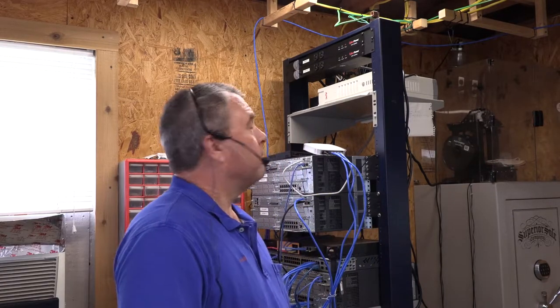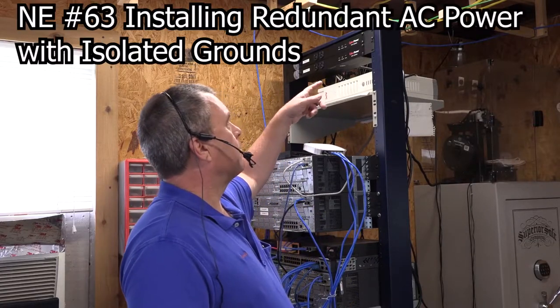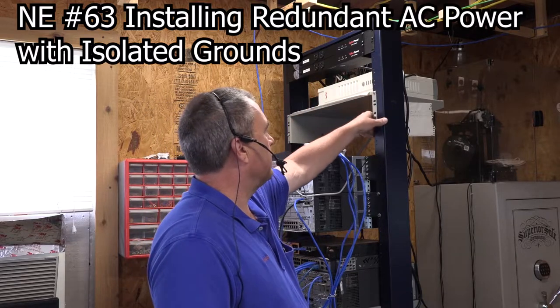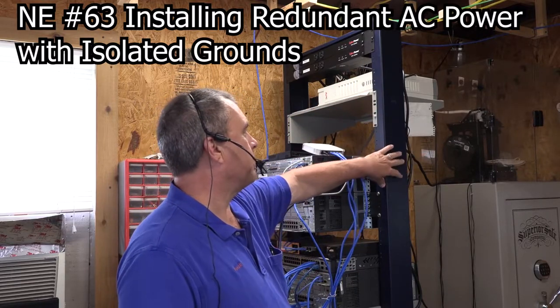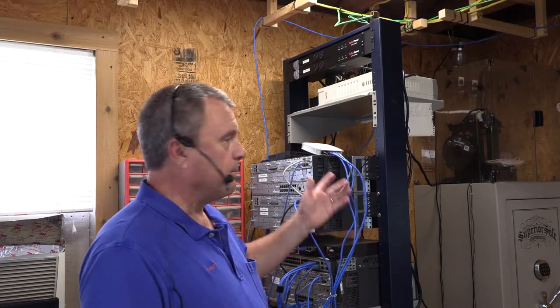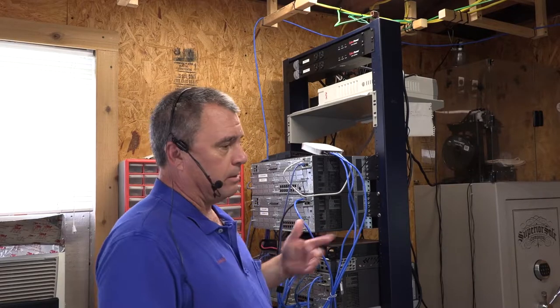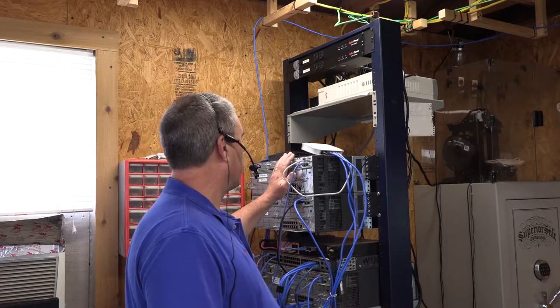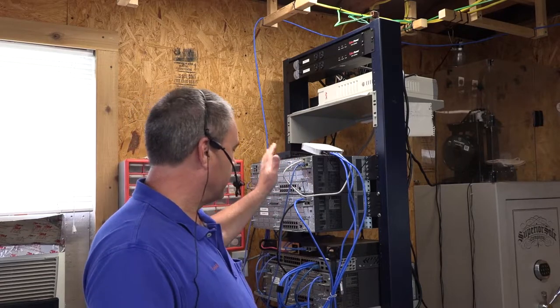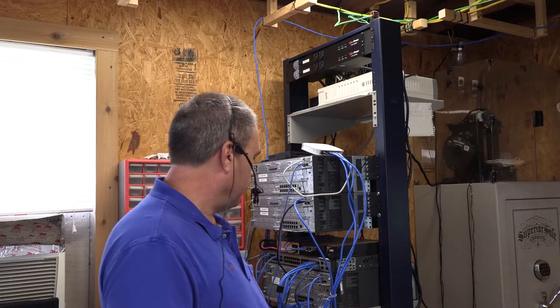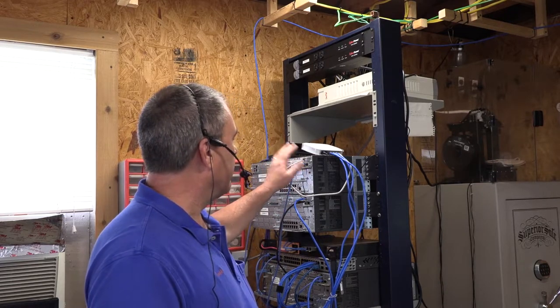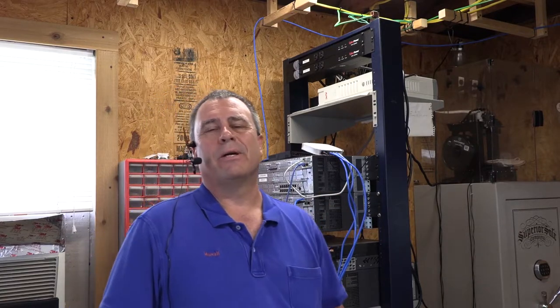Welcome to the Network Engineering Video Blog, I'm your host Michael Crane. If you remember in one of our previous videos, we put an isolated ground that's actually separate from the chassis ground in the rack ground to make it quieter with less noise for the equipment. The power supplies in these routers are floating, so the chassis ground is actually separate from the power supply ground. One of the viewers of that video said we installed these PDUs...